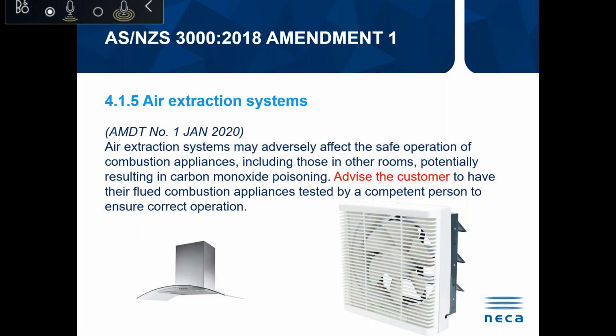One important point that you need to be aware of is if you are putting air extraction systems in, these include range hoods, fans, and the like, you must advise the customer to have their flued combustion appliances tested by a competent person to ensure correct operation. We at NECA are recommending that you note this on your certificates of electrical safety to show that you have notified the owner or occupier of a premises that they are required to have their gas equipment tested by a competent person to ensure that there's no carbon monoxide poisoning risk.